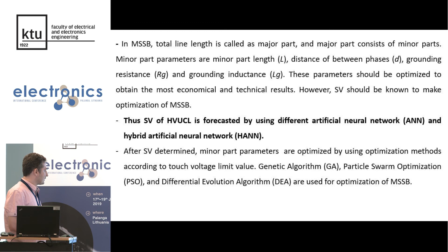Thus, SV of high voltage underground cable line is forecasted by using different artificial neural network (ANN) and hybrid artificial neural network (HANN). After SV is determined, minor part parameters are optimized by using optimization methods according to touch voltage limits value. Genetic algorithm, particle swarm optimization, and differential evolution algorithm are used for optimization of MSSB. In this study, high voltage underground cable is modeled in PSCAD simulation program, and simulation of high voltage underground cable lines are made to determine SV, sheath voltage. In PSCAD, different high voltage underground cable lines are modeled, and SV of these lines are measured.